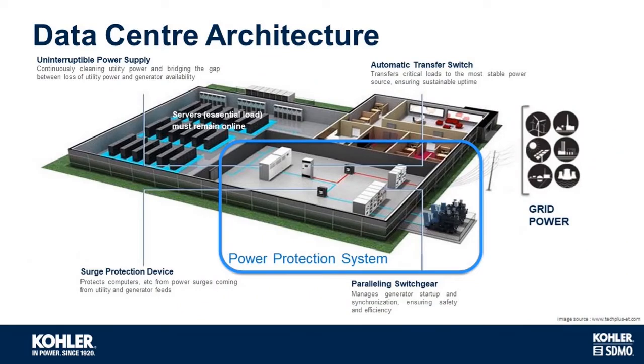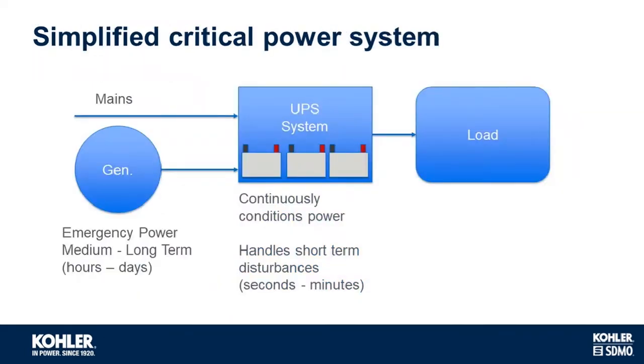At the heart of any data center's power protection system are, of course, the generator sets, the UPS, the transfer panels, and the switchgear. In this simplified example of an integrated UPS and generator system, we can see the UPS in the center, which continuously conditions the power and handles any short duration disturbances from a few seconds to a few minutes. We can also see the generator, which handles any long-term power outages, which can be from a few hours to many days.